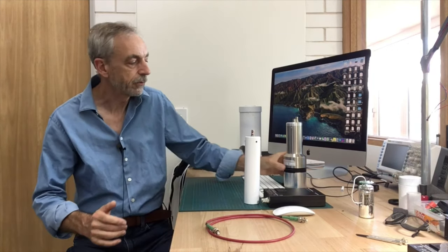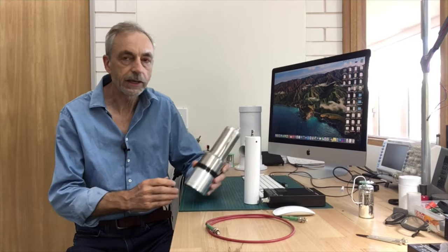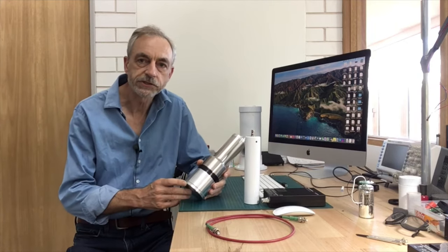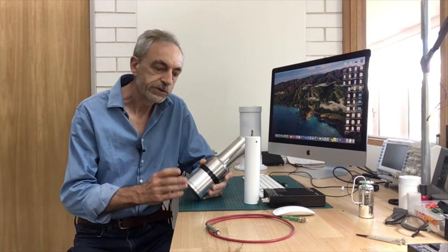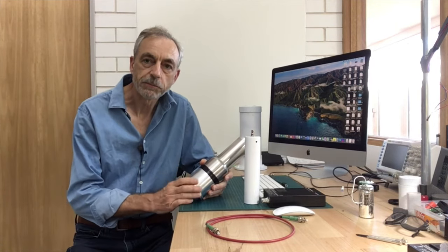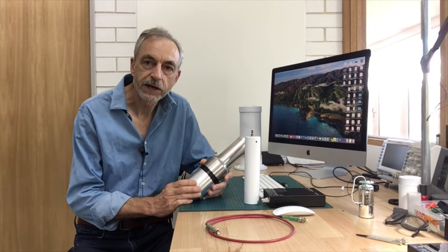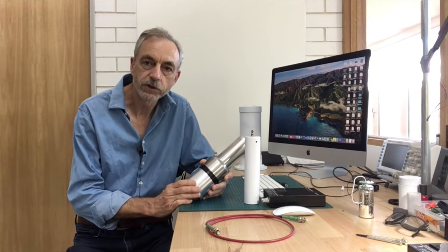If you are interested in gamma rays up to one and a half MeV then a crystal like the one and a half inch detector I have next to me here is fine. But if you want to look at the gamma rays up to and above three MeV then you will need something to see those gamma rays more efficiently. So that would be something like a three inch detector which is also more expensive and much heavier to work with.